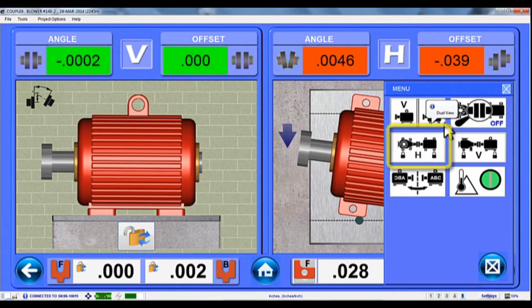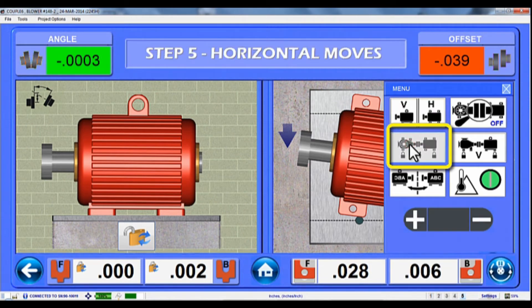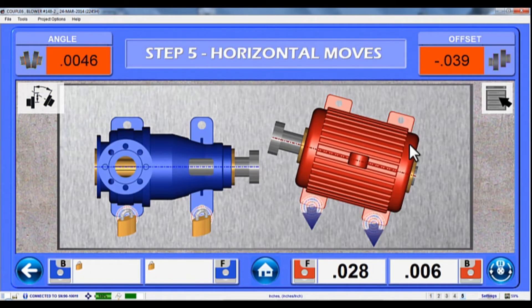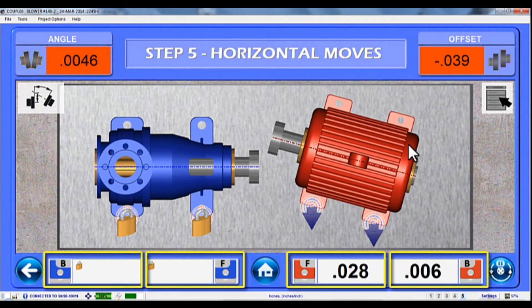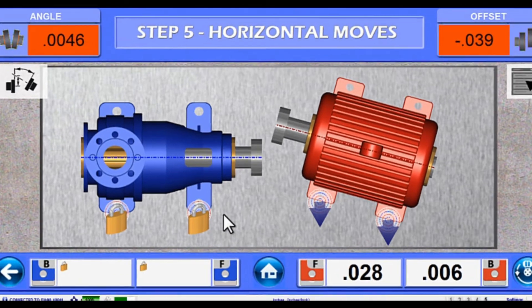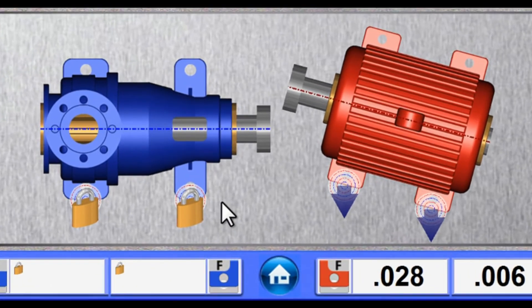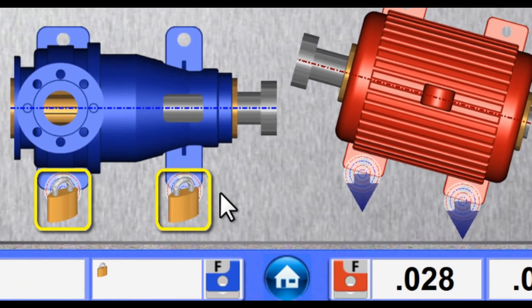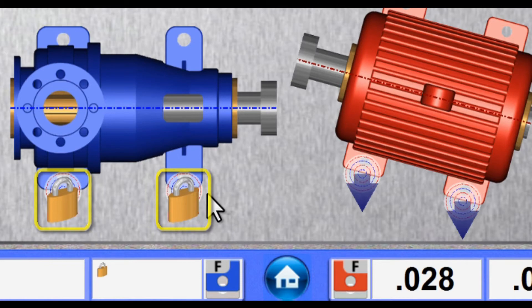There, select the Bolt Bound Horizontal screen from the View menu, and now you can see both the pump and the motor on the same screen with Move Value displays for both sets of feet. Notice there are lock icons over the pump's feet, which means Couple 6 will not calculate the shims for those feet.